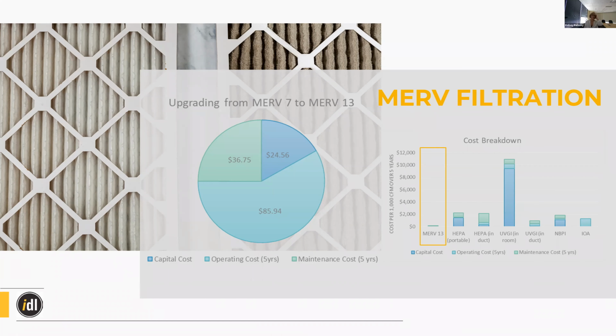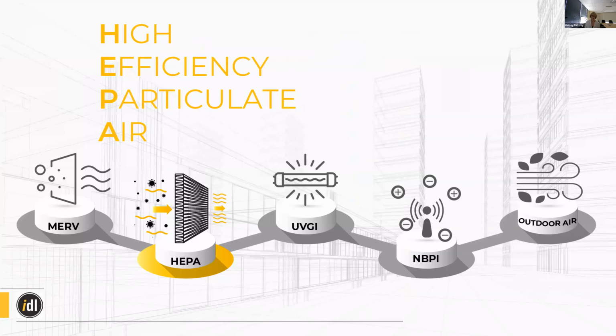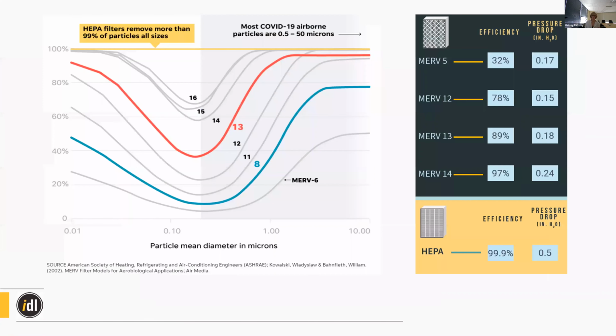So you'll see that capital costs are really low because basically you're already buying a MERV 6 filter. You just need to buy one that's a little bit more expensive. And then operating costs are the main cost associated with upgrading your MERV filter, just because the fan is going to have to work a little bit harder to get air through that finer mesh, but the efficiency associated is much higher. I'm going to go back real quick. Just right here, you'll notice a MERV 5 is rated at a 32% efficiency, where MERV 13 has an 89% filter efficiency.